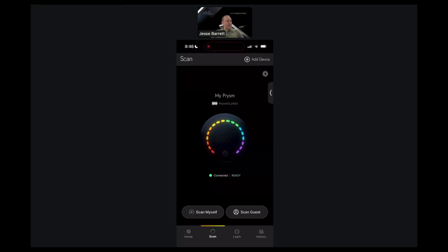And like I said, calibration is important. You don't have to calibrate it every single time you scan. I would calibrate it at least every week if you can. But if you feel like it might be scoring off, just go ahead and do another calibration. You could do it every 1 to 2 weeks, and you'd probably be fine.